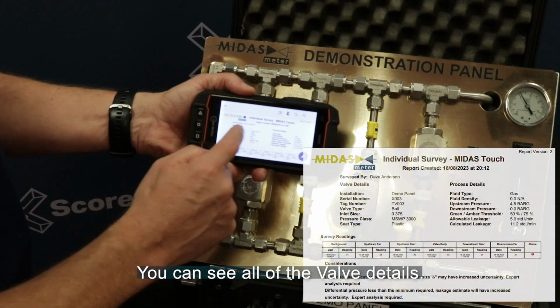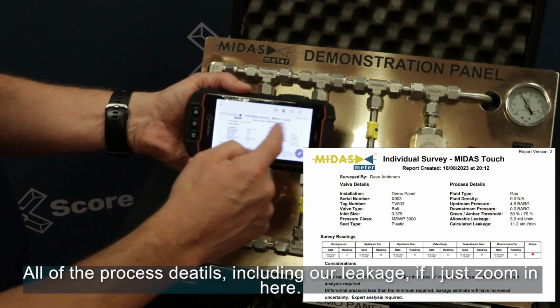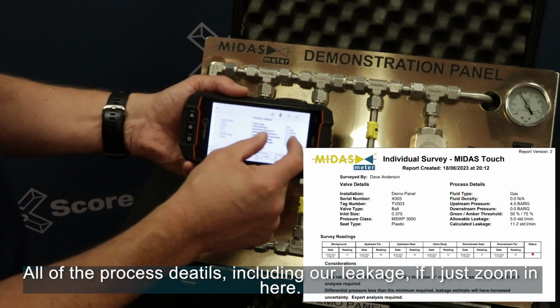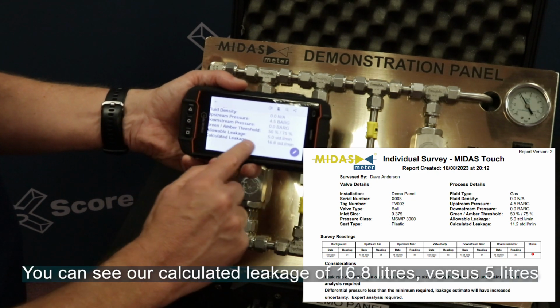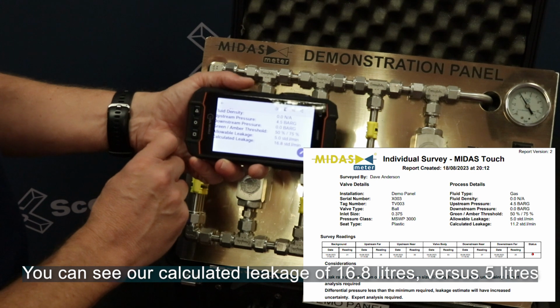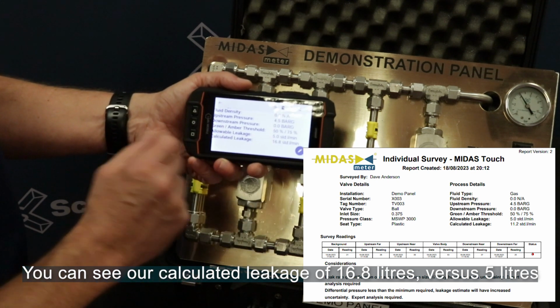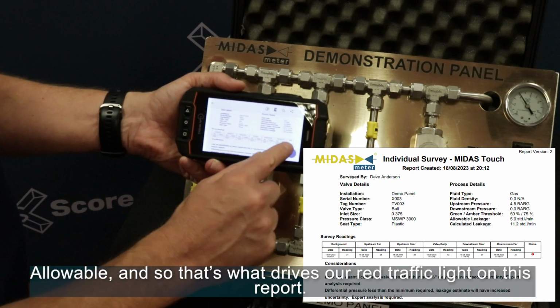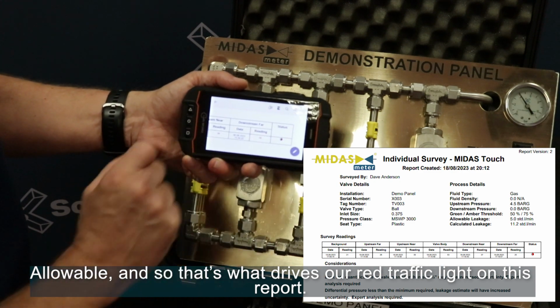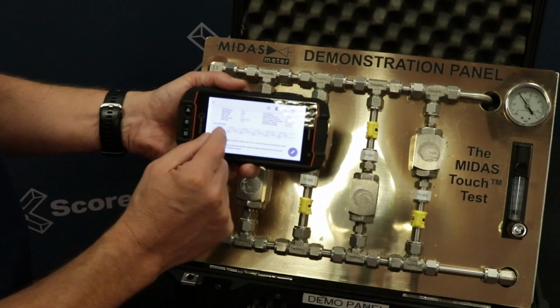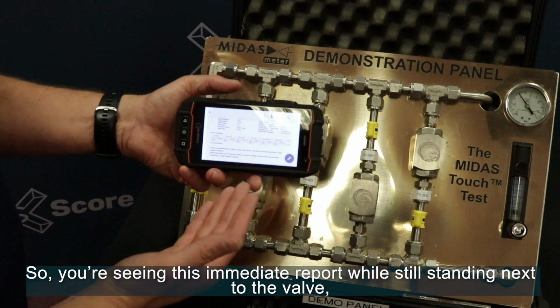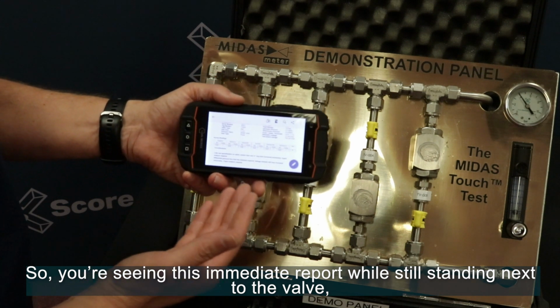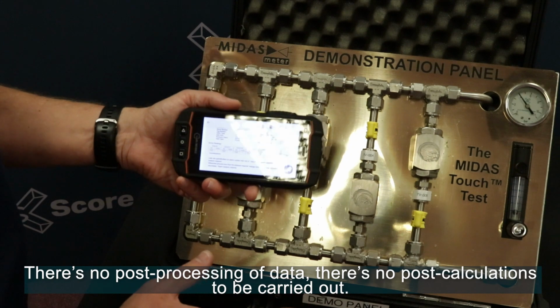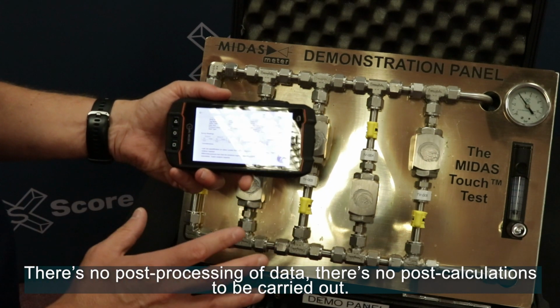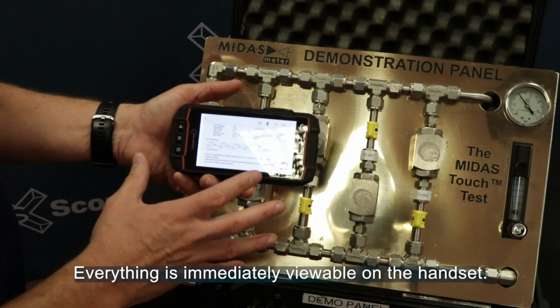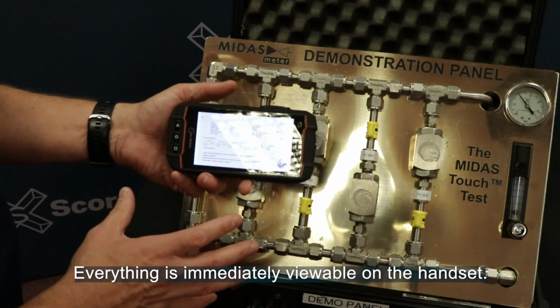You can see all of the valve details, all of the process details, including our leakage. If I just zoom in here, you can see our calculated leakage of 16.8 litres versus 5 litres allowable, and so that's what drives our red traffic light on this report. So you're seeing this immediate report while you're still standing next to the valve. There's no post-processing of data, there's no post-calculations to be carried out. Everything is immediately viewable on the handset.